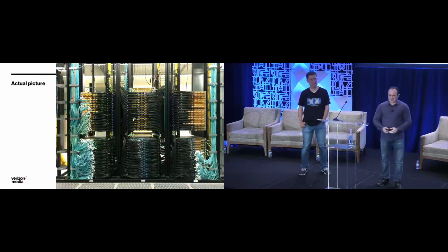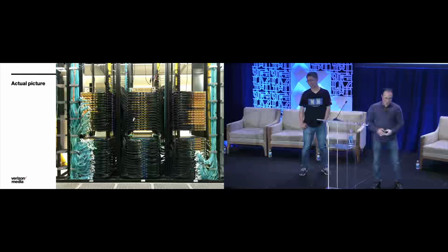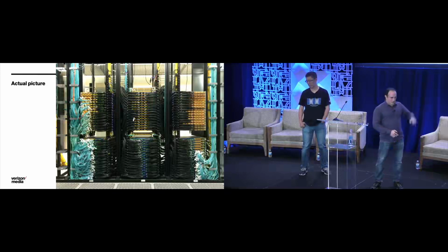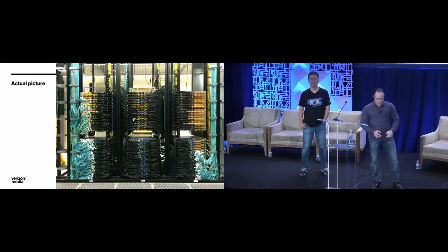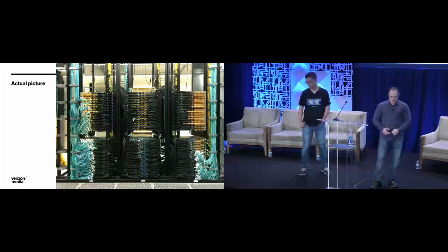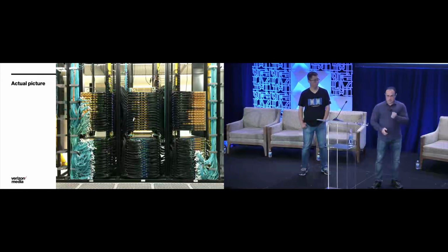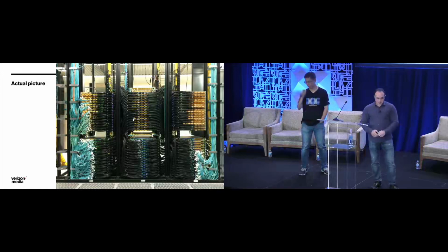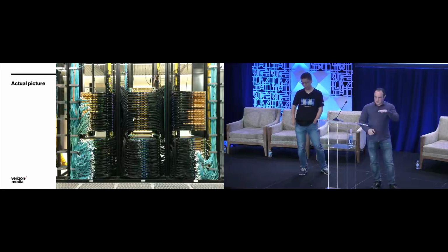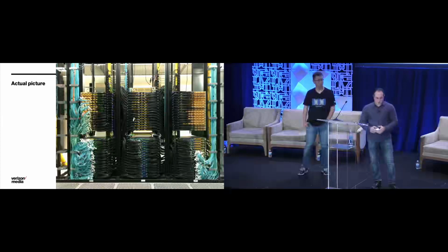What you're actually looking at is what's in production. This is two separate VCs. One is from cluster A, one is from cluster B, one on top of each other, essentially. As you can see, we've spent quite a bit of time designing custom length cable bundles to make miswiring incredibly hard because the cables are actually designed with less than a 2.5-inch tolerance. So when we pull something out, they almost stay right in place, and it's really hard to miswire.